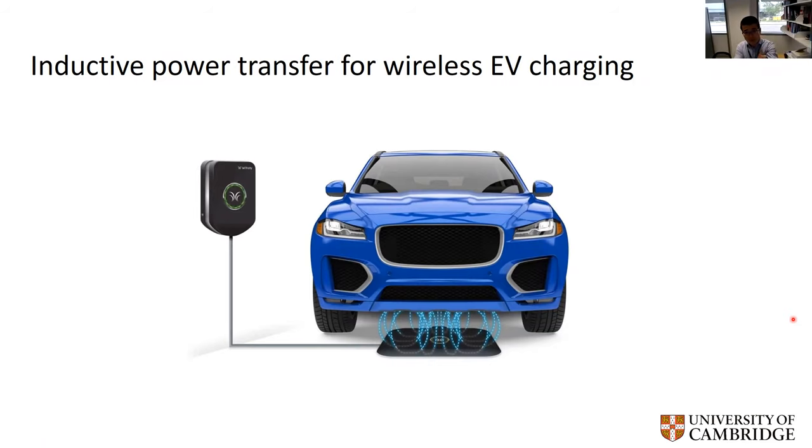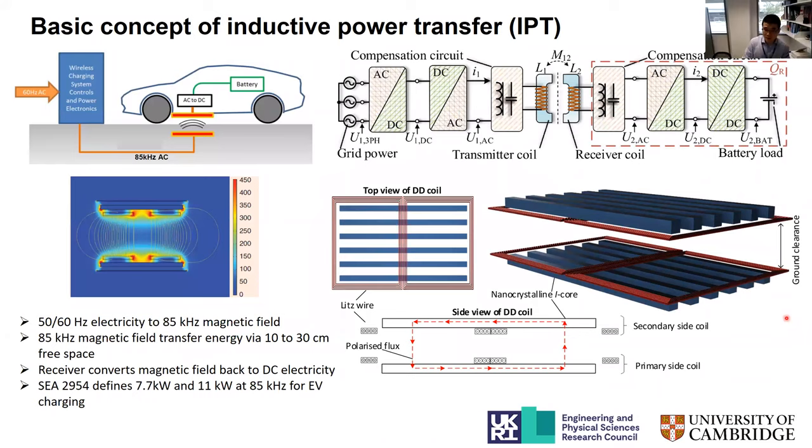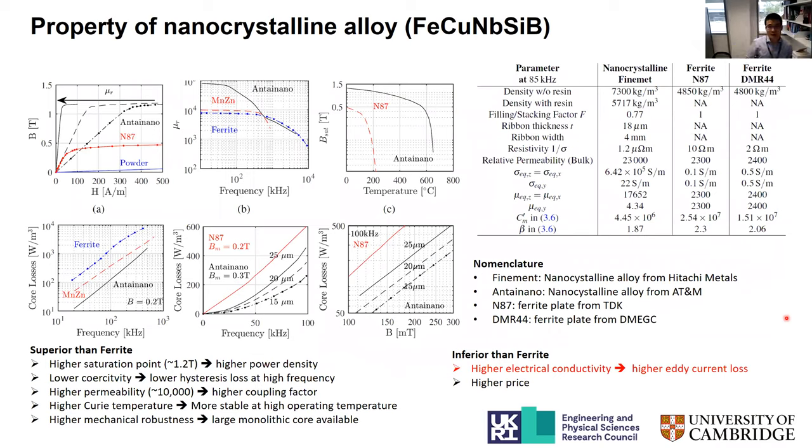Inductive power transfer for wireless power EV charging is also something we have been doing quite a lot. That was sponsored by EPSRC. We work on some high power transfer techniques, especially using different materials. We use something called nanocrystalline alloy, which is different to the conventional high frequency material, ferrite. Ferrites are very fragile and brittle, they are ceramic compounds, but nanocrystalline alloys are metallic materials. So they are more robust, and also have other good properties like a higher saturation point. Ferrite is only about 0.45 Tesla, nanocrystalline can go higher. That means you can have higher power for the same size. And technically it can also have lower losses if you design properly, but I'll talk about that later.